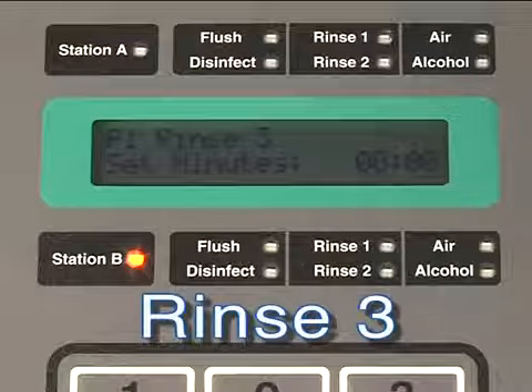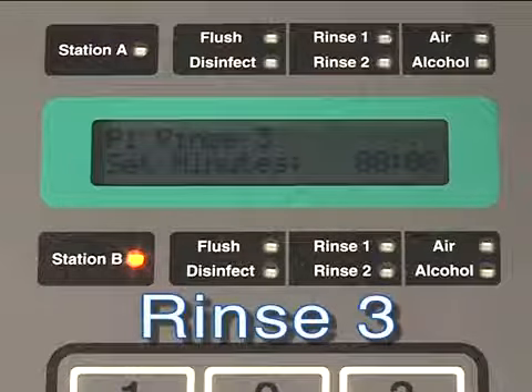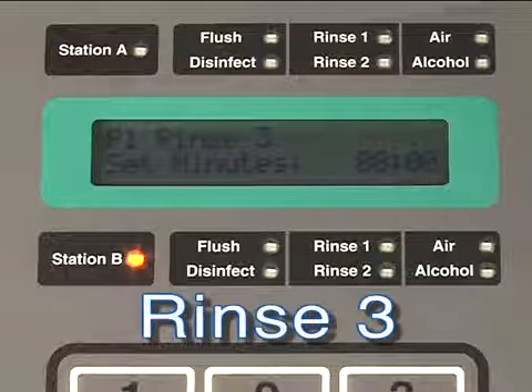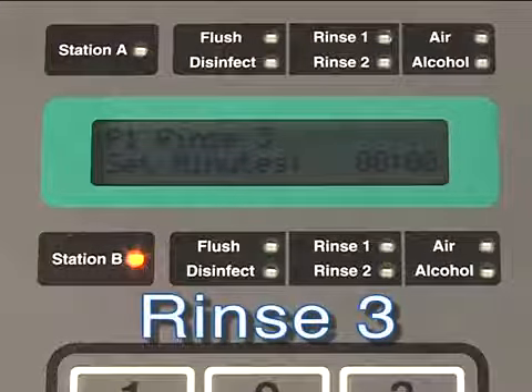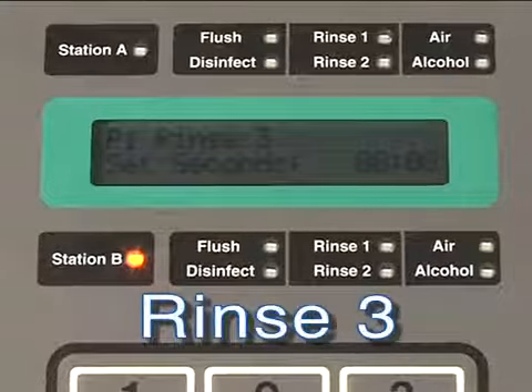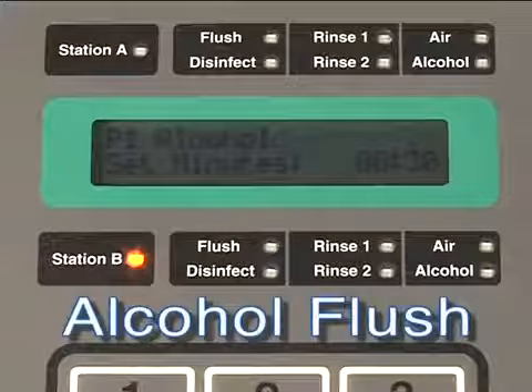The Rinse 3 screen is now displayed. Since Rapicide requires only 2 rinses, we will enter a 0 in for both the minutes and seconds screen to bypass the third rinse. However, if you are using a disinfectant like OPA, that requires a third rinse, you would program the third rinse here. The alcohol flush is the next parameter to enter.